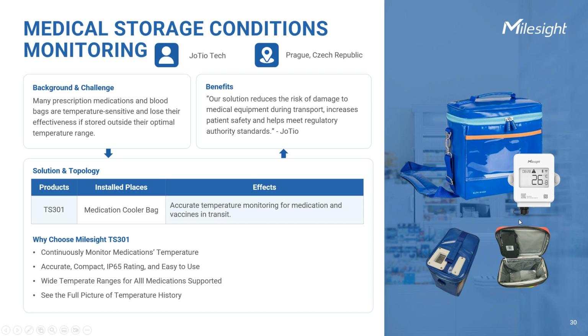The TS301 is a compact and powerful device measuring just 110 by 75 millimeters, suitable for all kinds of cooler bags. It offers a high measurement accuracy of plus or minus 0.5 degrees Celsius, making it a reliable companion for medications in travel. The PT100 probe can be placed inside the bag, continuously measuring the temperature and sending alerts if the temperature nears or exceeds safe levels.